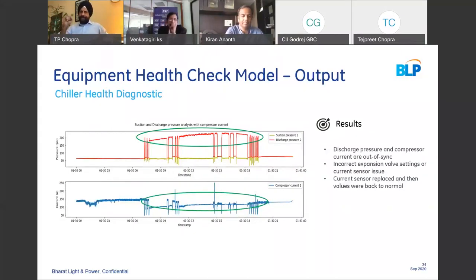A second area was chiller health diagnostics. The chart shows the suction and discharge pressure analysis compared with the compressor current. We found that the discharge pressure and the compressor current were out of sync, which was causing a huge amount of variance in the energy consumption of this building. In this case, we had to change the sensors and fix this out-of-sync situation to drive energy efficiency with the algorithms.